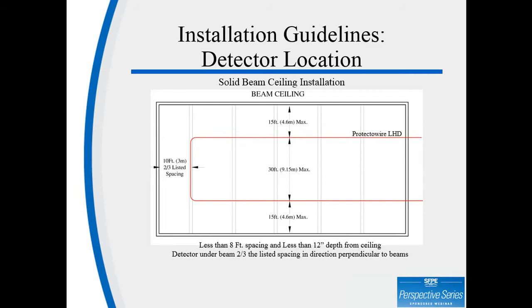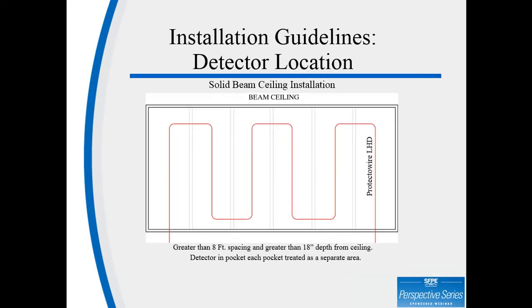LHD detector location on solid beam ceiling installations. In the case of beam construction, where the beams are 4 inches, 100 millimeters or less in depth, the ceiling shall be treated the same as a smooth ceiling. If the beams project more than 4 inches, 100 millimeters below the ceiling, the spacing at right angles to the direction of beam travel shall not exceed 2/3 of the smooth ceiling spacing. Where the beams project more than 18 inches, 46 centimeters below the ceiling, and are spaced more than 8 feet, or 2.4 meters on center, each bay formed by the beams shall be treated as a separate area requiring detector coverage.